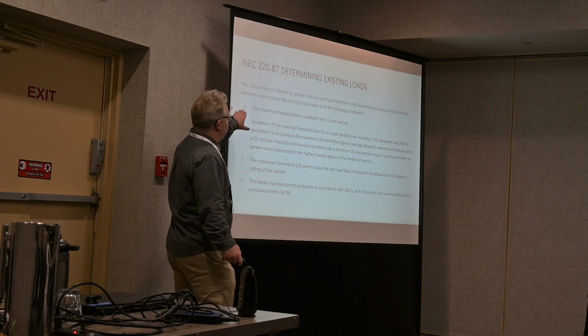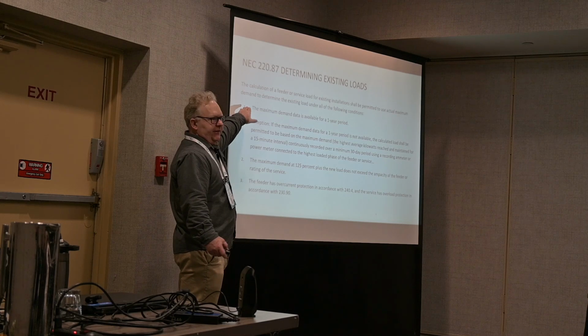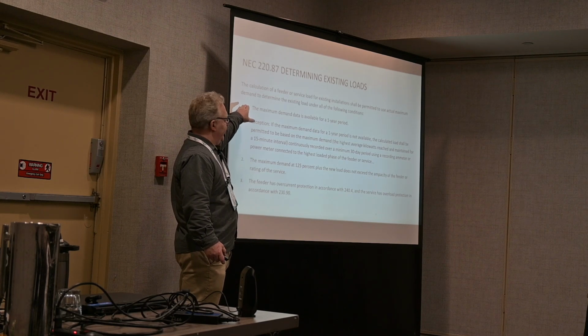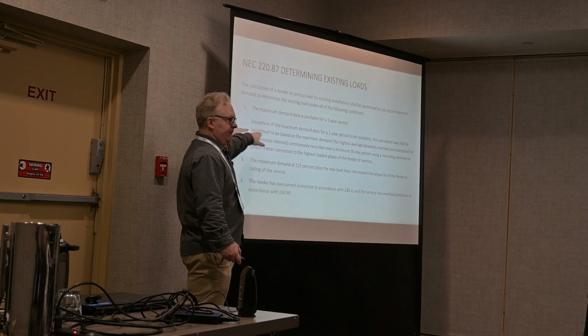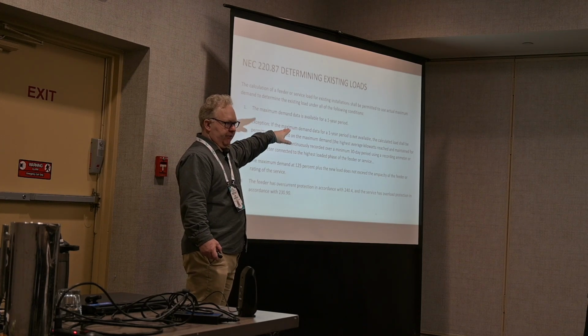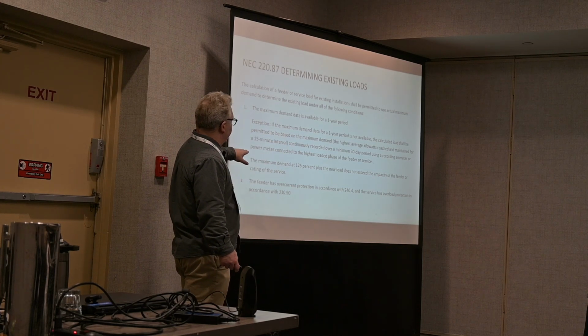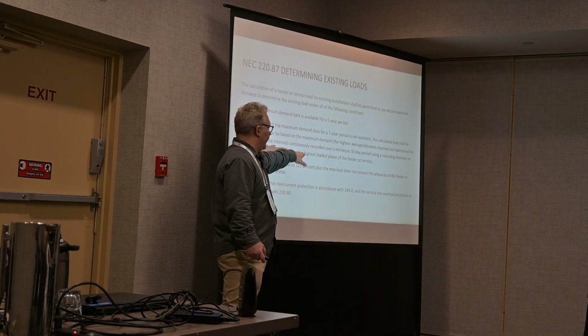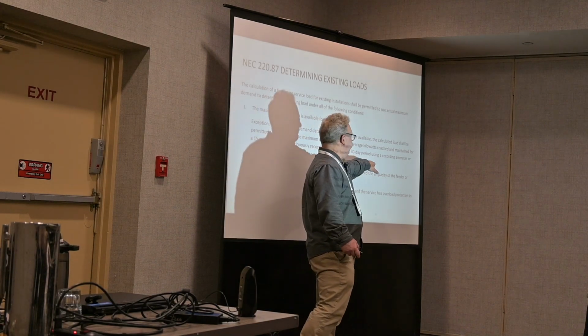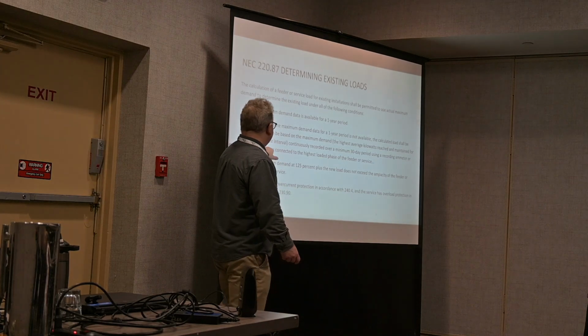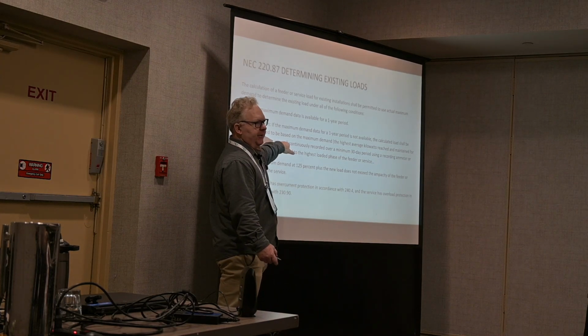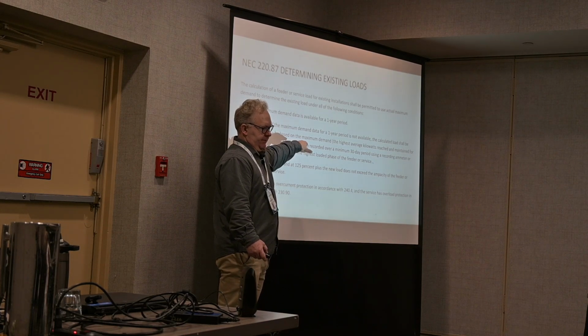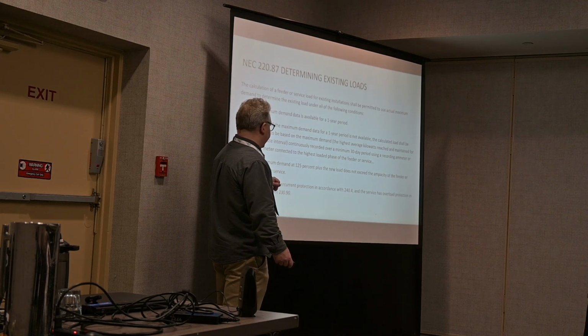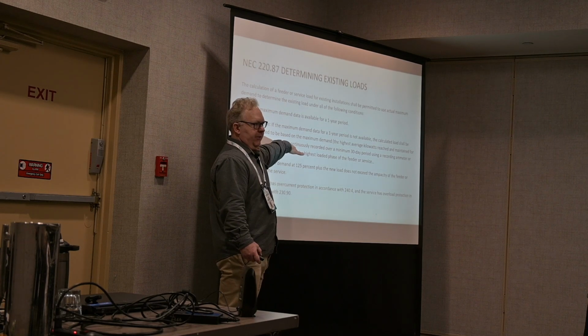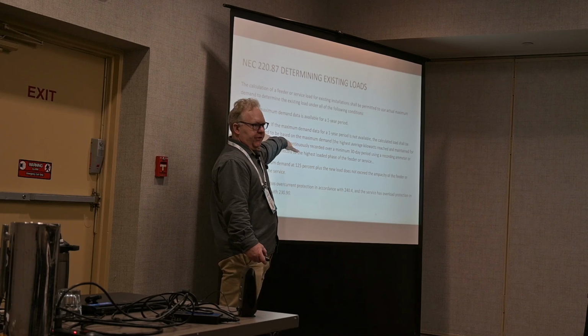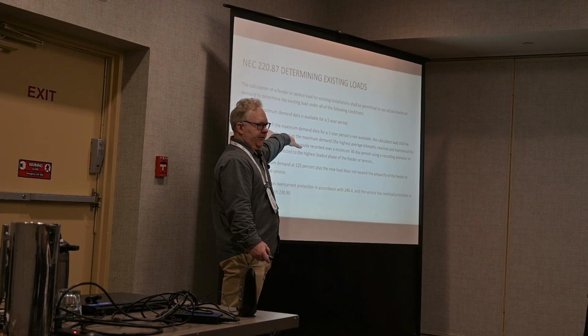Essentially, what the code says is you should have maximum demand for a 1-year period. But then there's an exception. If you don't have a year of data, which you rarely will, as long as you have a full 30 days of data, you can take the peak 15-minute interval during that 30-day period. And that will tell you your starting peak watt draw.